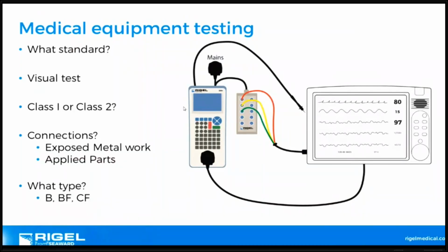It's also worth considering the visual test, very, very important to determine how good a condition the electrical equipment is in. And I'll go into some of the classifications of the visual test later on with 62353. Is it class 1? Is it class 2? Does it have exposed metalwork, which we need to put our probe on? How many applied parts does it have? And what type of applied part is on the medical device? So you might have multiple. The defibrillator, for instance, has BF and CF, and many devices have a mixture of types. These need to be identified and classified, and you can use a safety analyzer there.